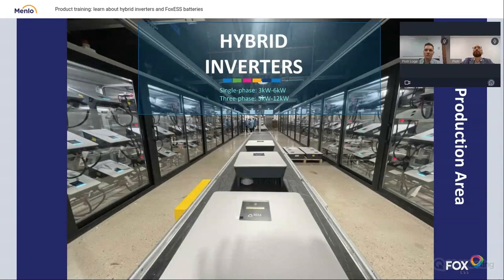Those hybrid inverters come in two flavors: one-phase systems and three-phase systems. You can compose such a system to your needs. If you want to set up a small building, a boat, or a camper, you will probably need a single-phase inverter in the lower nominal power ratings. Those power ratings are from 3 to 6 kilowatts per phase.